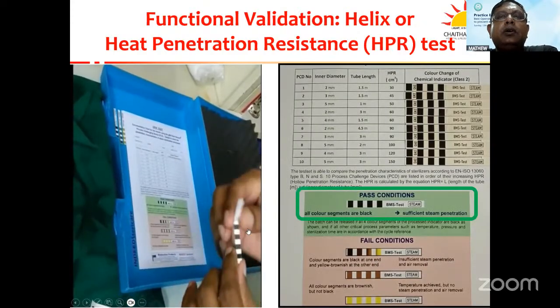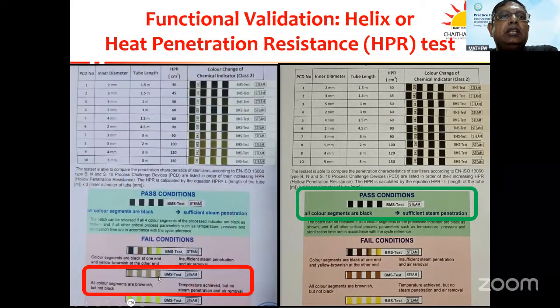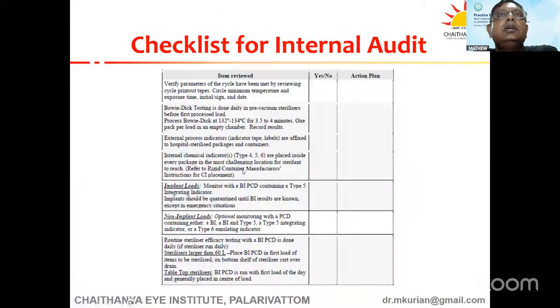And if it all becomes black, then these are the pass conditions, and we can have increasing resistance, and at least we should have HPR which is okay for greater than the longest tube that is going to go into the autoclave. And fail conditions will be like this, where the black is not formed, it is a light brownish one, in which case the sterilizer needs to be stopped and needs to be serviced.